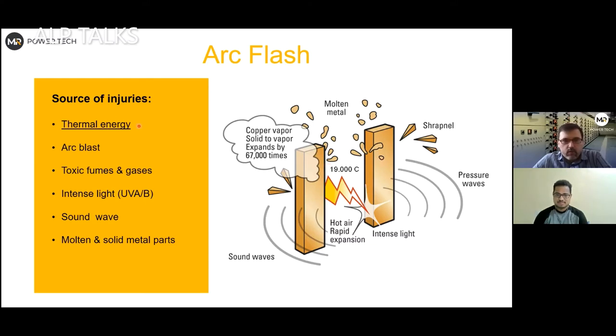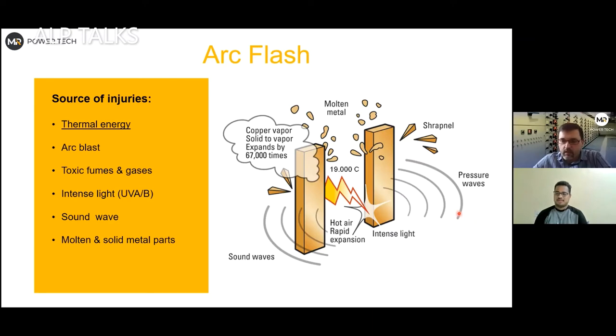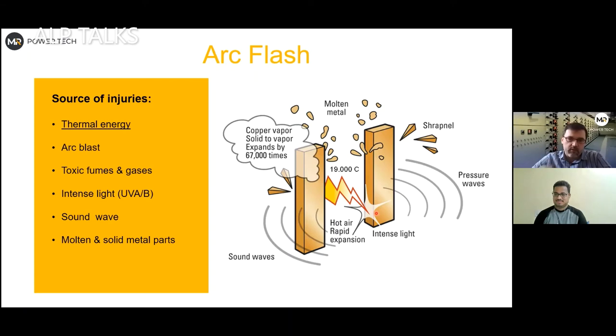We are most worried about the thermal energy — that's the main concern. You also saw small flying particles of copper or aluminium, which can be solid or liquid. There's also a pressure wave, like an explosion — something like 100 up to 160 decibels. Above 140 dB you have ear damage. There's intense uncontrolled light, about 100 times brighter than looking directly at the sun, plus UVA and UVB radiation — that's why arc flash shields come in different colors to protect the eyes.